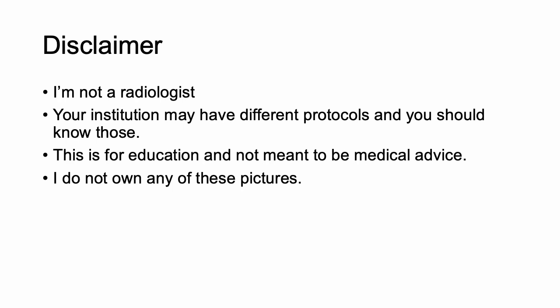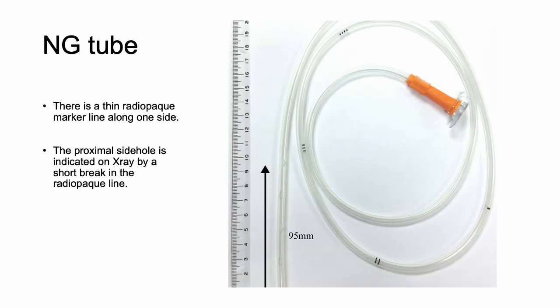This is what your typical NG tube looks like. I want to especially point out that there is a radiopaque marker along the side, and then the proximal side hole. You can see there are holes here — the proximal side hole is indicated by a short break in the radiopaque line. It's important to know where this side hole is, and we will go over that in the next couple of slides.